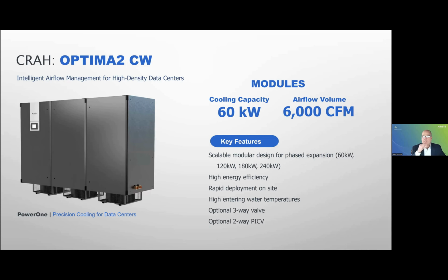Then we have our Optima 2 chilled water product up to 240 kW. This product is truly an offset of our CRAC unit DX Optima 2 product set. It comes in modules, so you can build it in 60 kW and add on to it to make it 120, 180, and 240 and above. Again, this modularity gives us the ability for rapid deployment, front and rear accessibility, so you can put them right up against each other. And they come in a number of different configurations: downflow, upflow, front discharge, rear discharge. Piping is unhanded, so you can come in from the top, the bottom, the left, or the right.